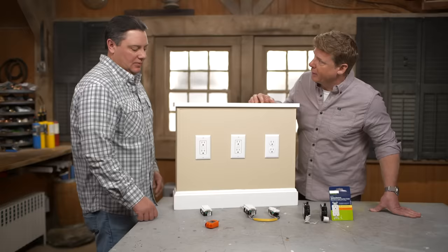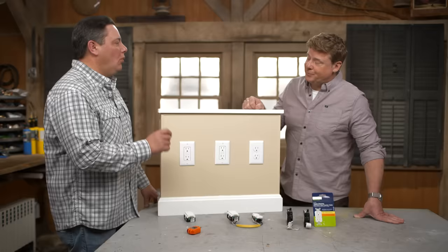So what's the smarts? How are they actually working and what are they doing? So what they're doing is they operate by sensing how much current's being used by a device. When you plug something in, it's using a certain amount of current. This wants to see the same amount of current on both sides coming in and going back out. If it sees something as small as five milliamps of a difference, it knows it's losing current somewhere and it shuts down to protect you. That's a tiny amount. Tiny, tiny amount. It's thinking it went to water, it went to a metal pipe — it went somewhere that it shouldn't go. So it shuts down.